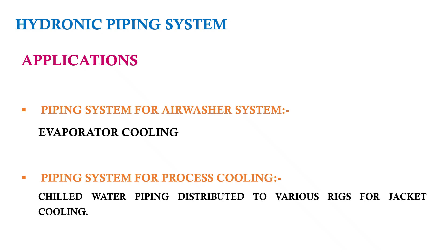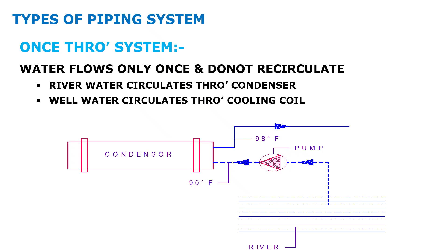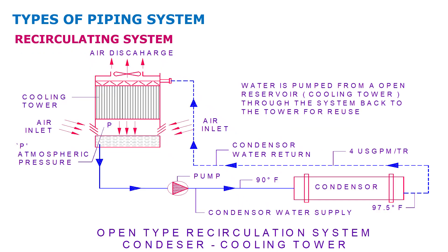In this video and the hydronic series, we will not calculate sizes, which will be covered separately, but we will understand what configurations can be used while designing any hydronic system. The once-through system is one where water comes from a river, takes heat from the condenser, and goes back to the reservoir — the same water does not return. An open pond can also be used to reject the condenser heat of a chiller.